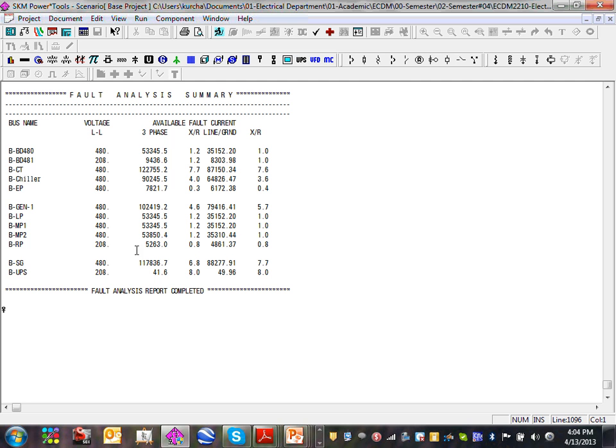So that's kind of the short circuit on the switchgear. If you look at the MP1, guys, mechanical panel, there's 53,000 amp short circuit on it, so I need equipment rated for 65. Same thing for MP2. Receptacle panel, look at the receptacle panel. I have only 5,000 amp on my receptacle panel. It makes sense because it's 208/120, very small.